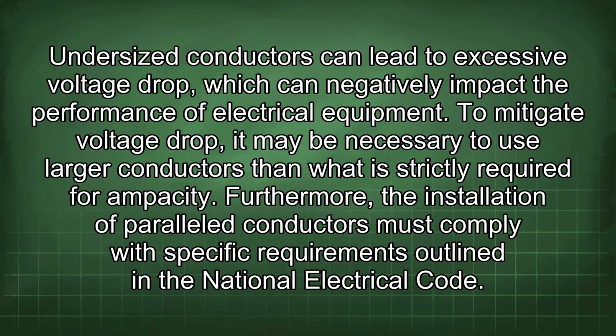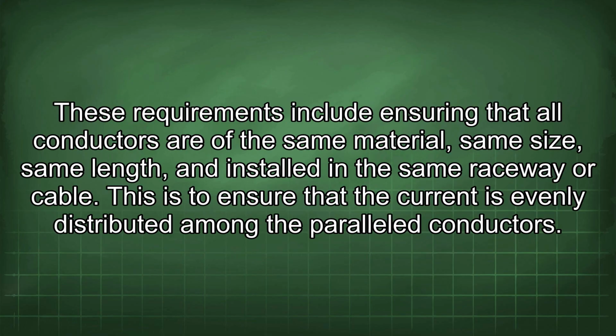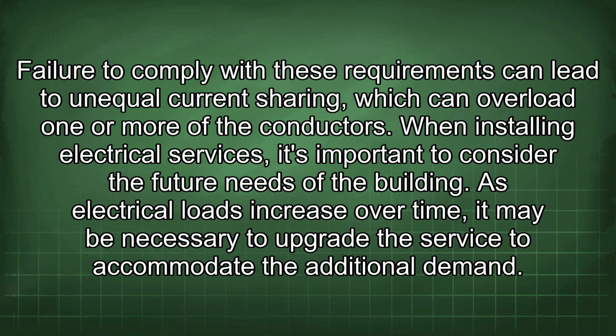Furthermore, the installation of paralleled conductors must comply with specific requirements outlined in the National Electrical Code. These requirements include ensuring that all conductors are of the same material, same size, same length, and installed in the same raceway or cable. This is to ensure that the current is evenly distributed among the paralleled conductors. Failure to comply with these requirements can lead to unequal current sharing, which can overload one or more of the conductors.